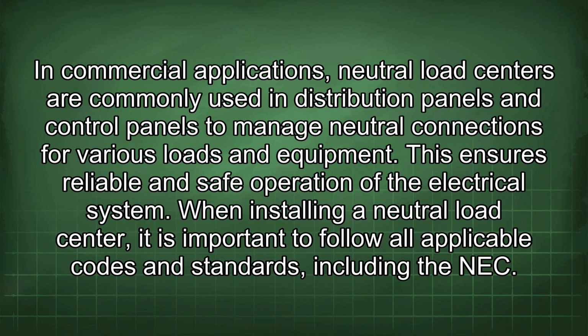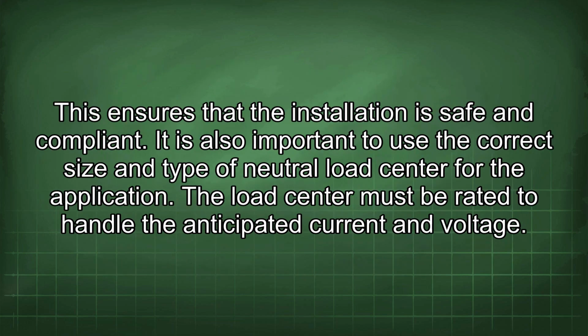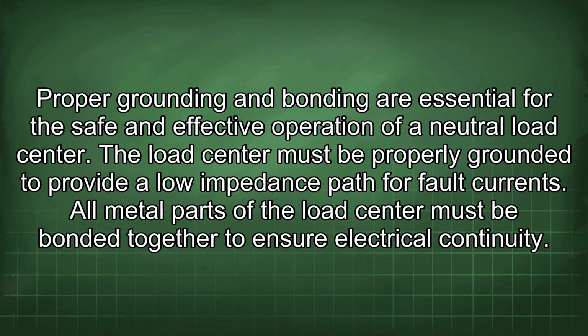When installing a neutral load center, it is important to follow all applicable codes and standards, including the NEC. This ensures that the installation is safe and compliant. It is also important to use the correct size and type of neutral load center for the application. The load center must be rated to handle the anticipated current and voltage. Proper grounding and bonding are essential for the safe and effective operation of a neutral load center. The load center must be properly grounded to provide a low impedance path for fault currents. All metal parts of the load center must be bonded together to ensure electrical continuity.